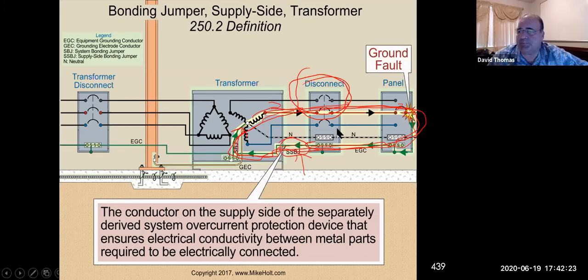Okay, now what we do in ungrounded systems is we have ground fault detectors, and that's how we can avoid this. And so sometimes we will do ungrounded systems. Like, for example, that tomato processing plant, there was a pump that was so critical that we actually ended up doing an ungrounded system for that pump, that motor, because if that went out, it would actually cause pressures that could explode a chamber that they had over there in the tomato processing plant.